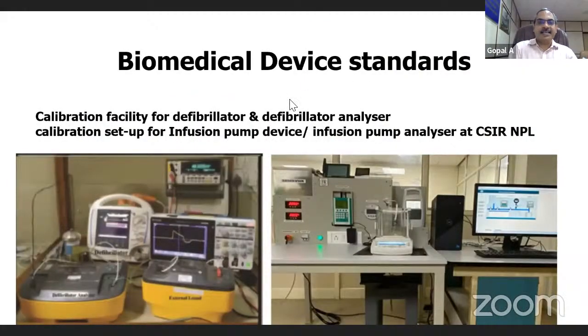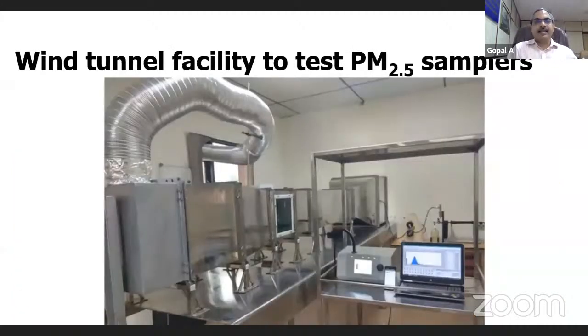So these are biomedical device standards which we are working on currently. For example, in January, the Honorable Minister dedicated to the nation a calibration facility for defibrillators, which are used for reviving patients by giving shocks, right? And also infusion pumps and infusion pump analyzers have been set up and made available to the country, right? So this is a wind tunnel facility to test particulate matter of 2.5 micron, 5 micron or 10 micron. So you need to precisely measure the particle sizes. The samplers which are used need to also be calibrated and tested, whether they are measuring the right counts or not.